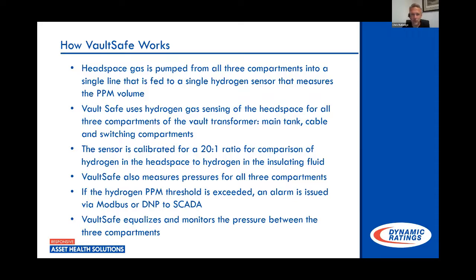So -2, -3 psi. Now, this creates another problem with the transformer, in that you're steadily pushing and pulling on these gaskets. You're applying pressure, and then you're sucking in on them, and then you're applying pressure, sucking. So you get wear and tear of that gasketing system, and it just expedites the chances of moisture ingress and having leaks. However, with the monitoring we built, since now everything's manifolded together, we now have that much larger compartment of the main tank where your core and coils are contained. So the pressure is able to equalize out across all the compartments, and you don't see such a rapid swing from vacuum to overpressure happening.